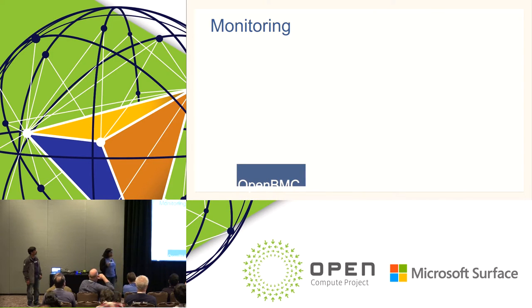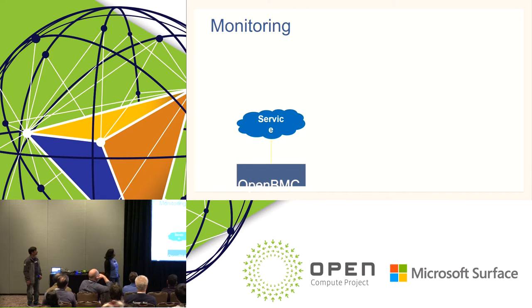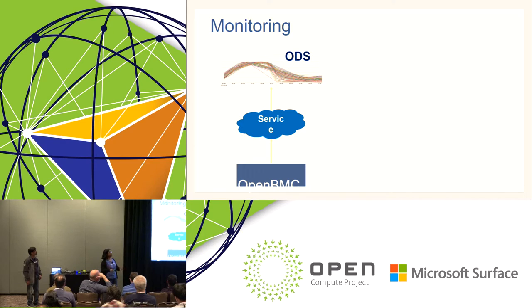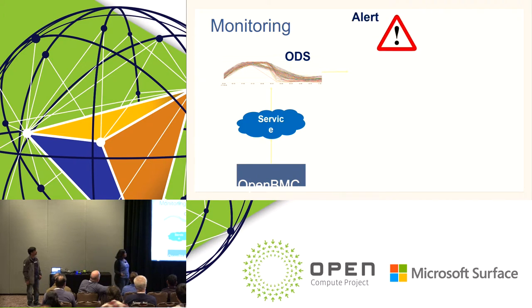For monitoring: OpenBMC lets us monitor many hardware components like fans, power supplies, and everything that comes with the hardware. We run an external service that pushes and pulls data from OpenBMC. This service constantly pulls information and pushes it to our internal monitoring system called ODS — a real-time monitoring system that detects anomalies. For instance, we get fan RPM data from OpenBMC; if a fan dies, the reported RPM would be zero, which is an anomaly that ODS detects and creates an alert for.